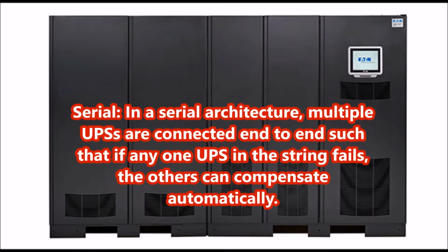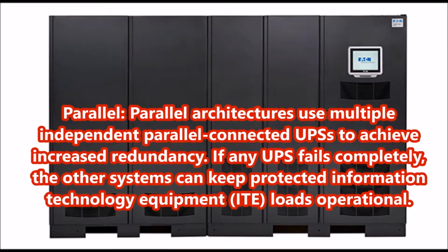Serial. In a serial architecture, multiple UPSs are connected end-to-end such that if any one UPS in the string fails, the others can compensate automatically. Parallel. Parallel architectures use multiple independent parallel connected UPSs to achieve increased redundancy. If any UPS fails completely, the other systems can keep protected information technology equipment (ITE) loads operational.